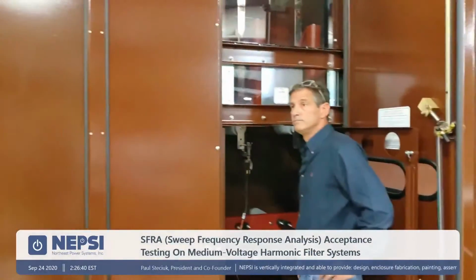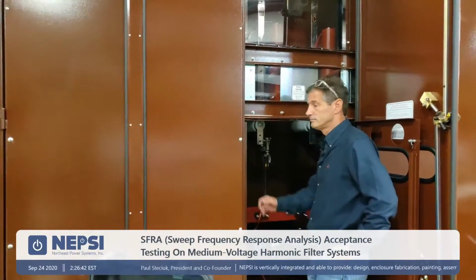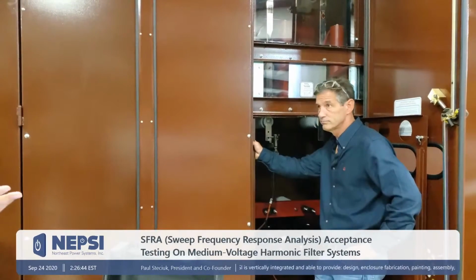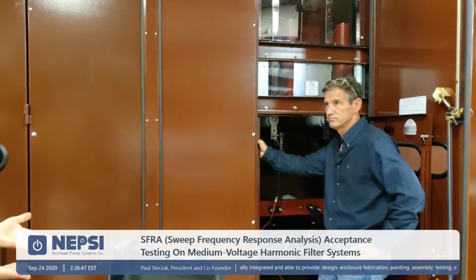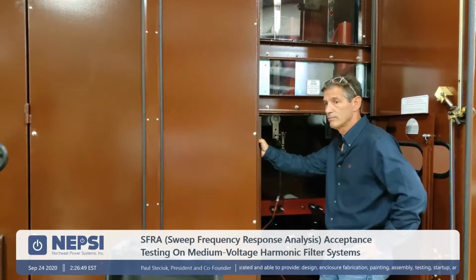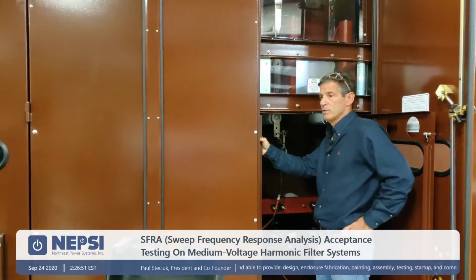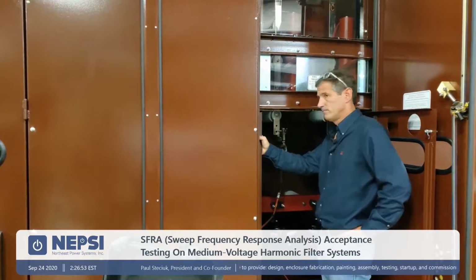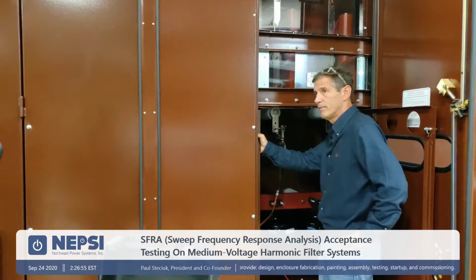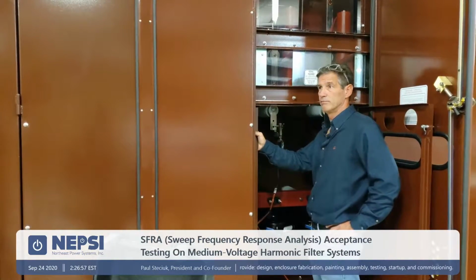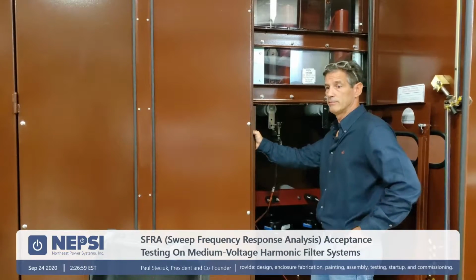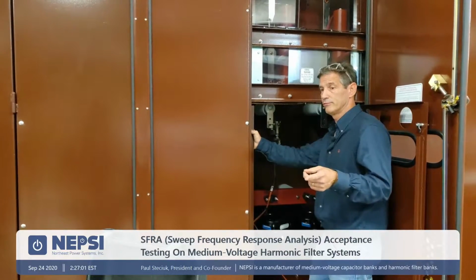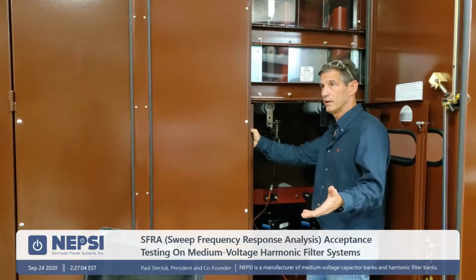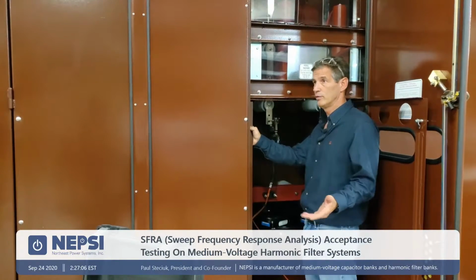So it's interesting, at the tuning point you would expect something very low because X of C equals X of L at the tuning point, and it's just resistance at that point. And this instrument can show resistance also, correct? Yeah. All right. Okay, so I'm going to disconnect A, and we're going to test B to C now, and Jessica will repeat this test, and then we'll overlay it on top of the first test. And that's the way we do this procedure.